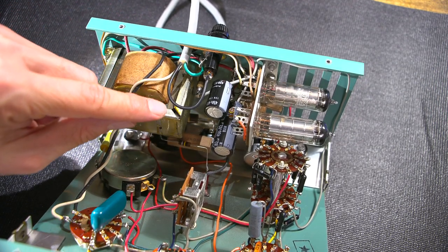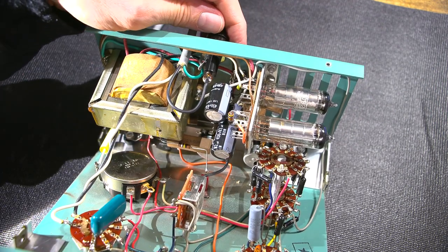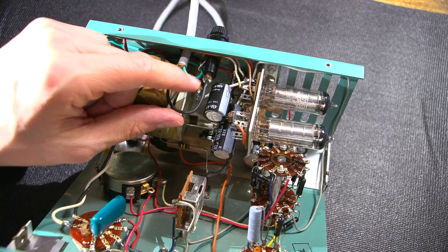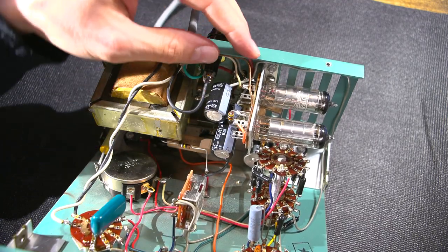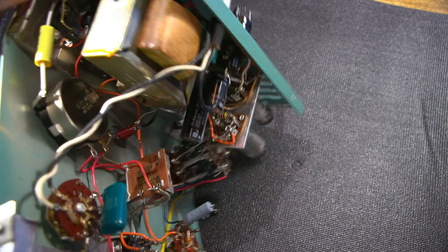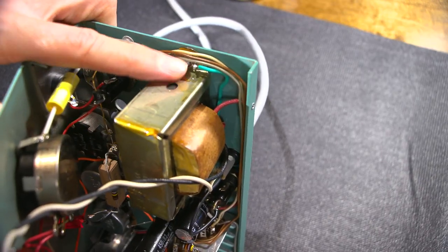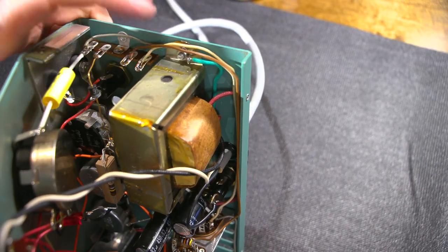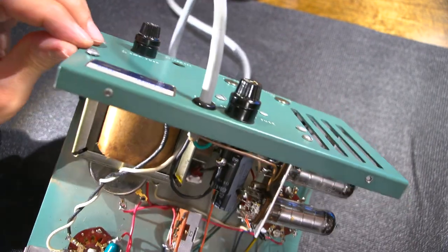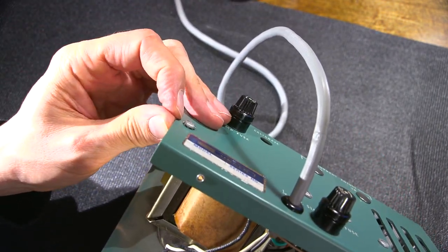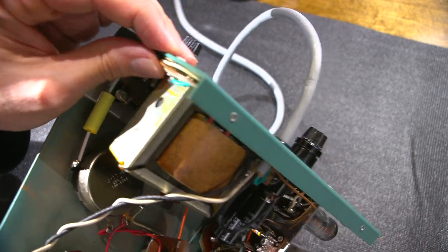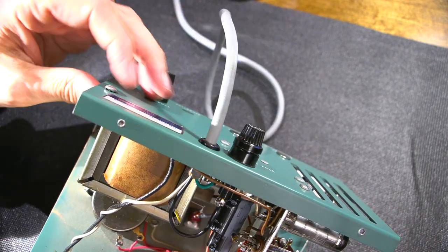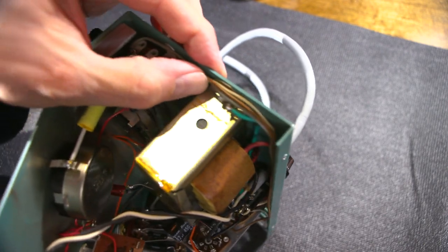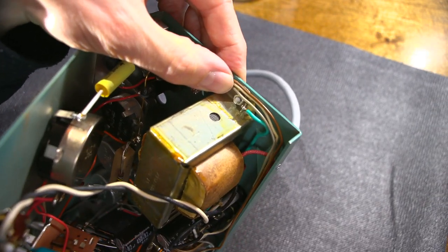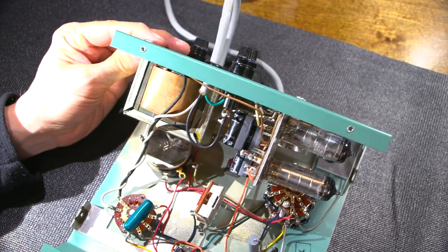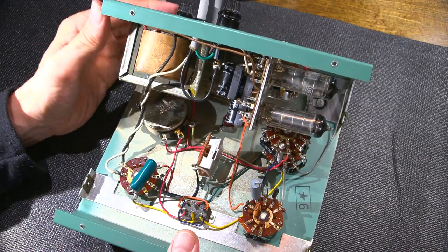There's a strain relief here because when you're changing the fuse, this moves around. So there's a strain relief right here. And then the ground goes to this point right here, and there's a star washer under there, and there's now a star washer on the back side as well to make sure that there's lots of ground. You'll notice that the other screws do not have star washers and this one does. I want to make sure that the paint is definitely broken through and that I have a nice solid earth on the back side.